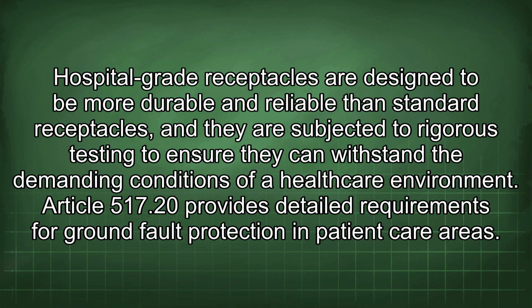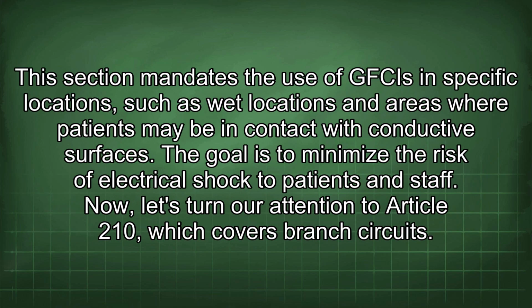Article 517.20 provides detailed requirements for ground fault protection in patient care areas. This section mandates the use of GFCIs in specific locations, such as wet locations and areas where patients may be in contact with conductive surfaces. The goal is to minimize the risk of electrical shock to patients and staff.